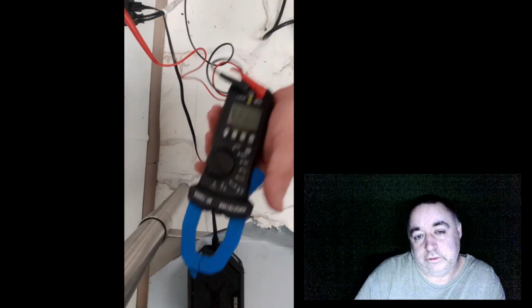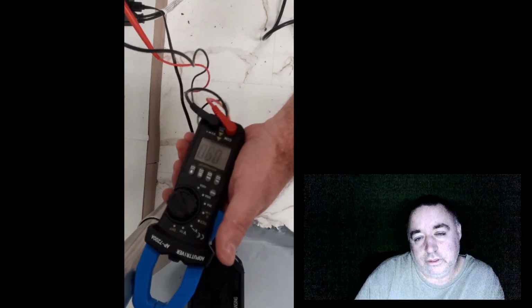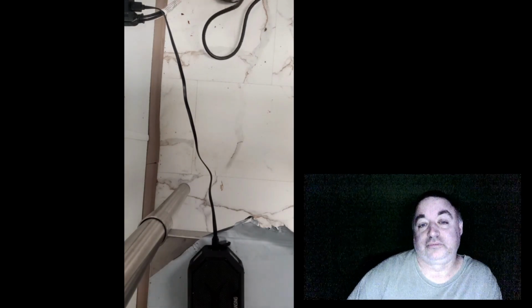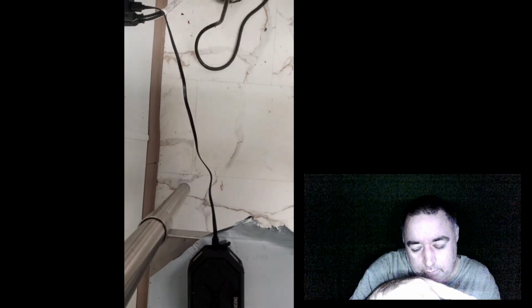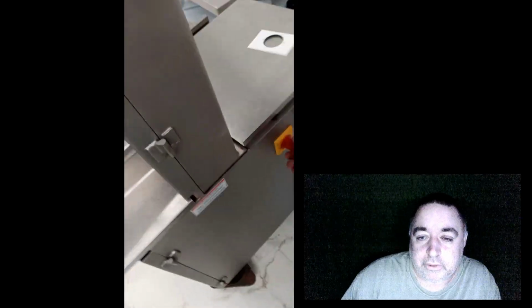Screw it. My clip came off. Those clips, I think I got at either Home Depot or Lowe's. Those universal meter leads with the alligator clips. They're pretty good. They fit the meter just like the originals. They're longer, and I love the alligator clips. Cannot have a meter without being able to clip. So I got full power on all 3 legs. I already checked the plug wires. But watch what I find next. Watch this. That's all good. I did take the plug apart. My 3-phase plug's locked. The three screws on the plug, just a basic locking plug comes apart. So I did take that apart. I think I filmed that.